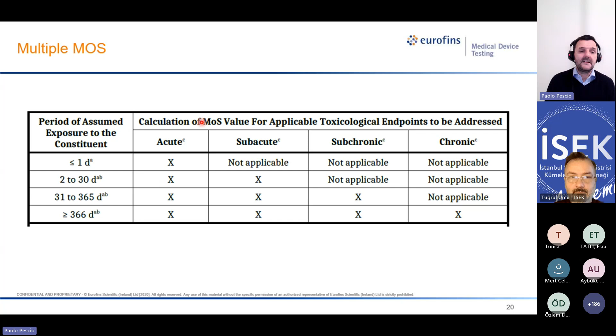If you have a device that is less than or equal to 1 day, of course you are just interested in acute effects. If the device has a contact that is more than 1 day, you are interested both in acute and subacute effects, and so on and so forth. When you have a permanent device, you are interested in the determination of the margin of safety for acute, subacute, subchronic, and chronic effects. You can easily see here how they correlate well with the systemic effects: acute, subacute, subchronic, and chronic effects. The very same effects that we need to address in the biological evaluation.